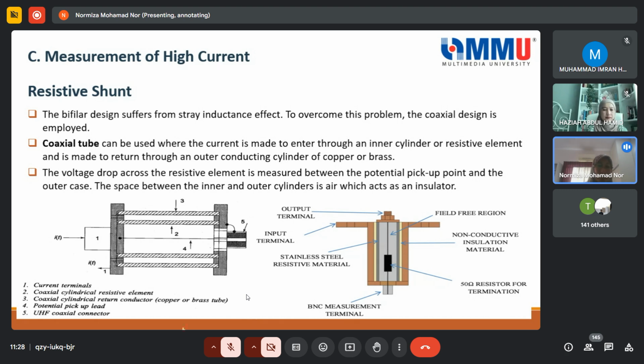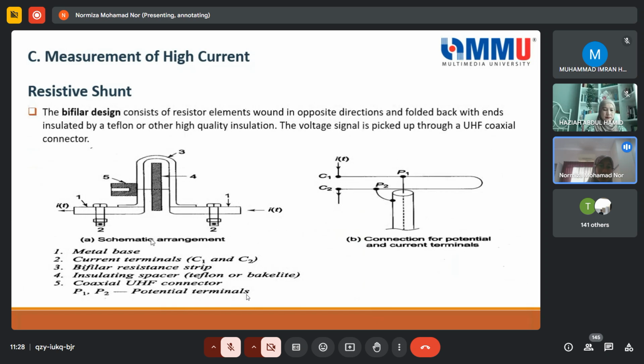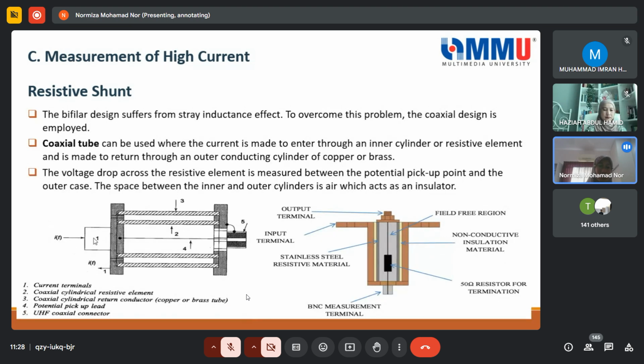So this is mainly for research. You can see the material used now has to be Teflon or other metal base, or other quality insulation. And this shape here has to be coaxial so that you can reduce the inductive effect. And then the voltage across the resistive shunt element is measured between the potential pickup point and the outer case.